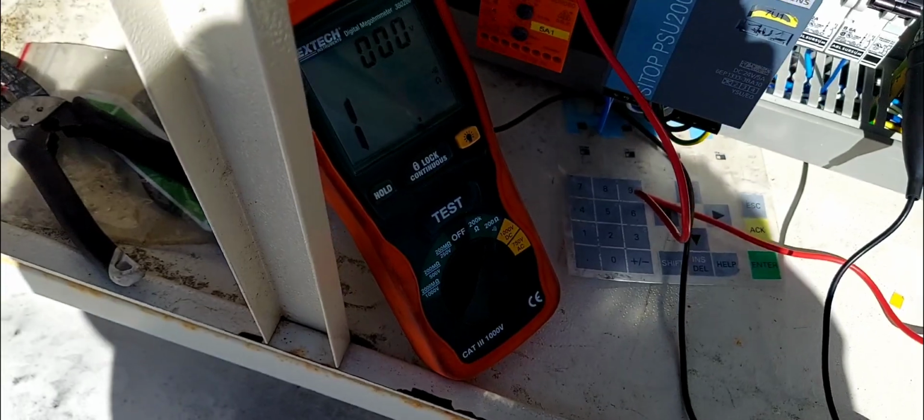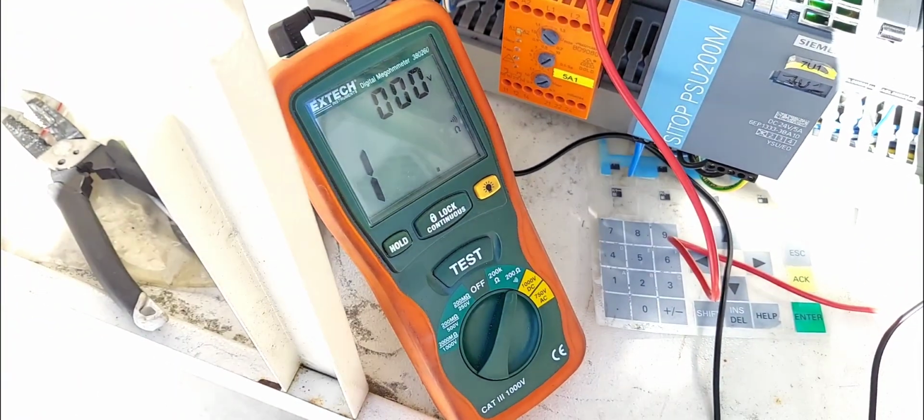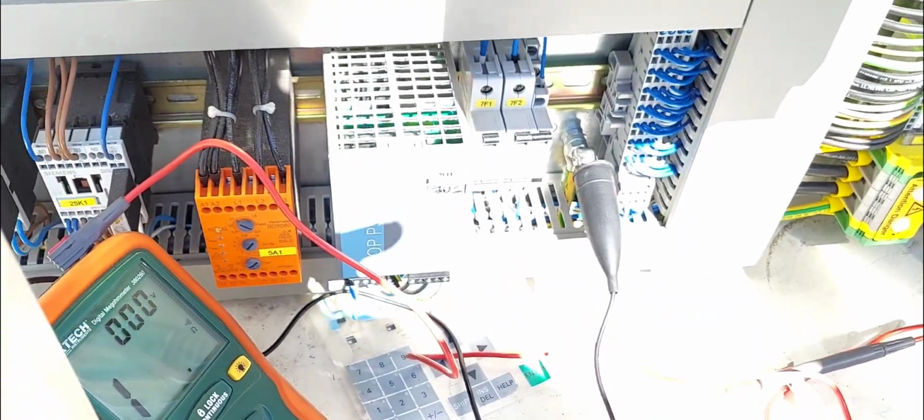Okay, so I have my meter all hooked up and ready to go. My negative probe, my positive probe. All right, so all ready for testing. I have the negative, the black, attached securely to the ground, chassis ground or any ground in the unit. You can go on your compressor discharge pipe or your suction pipe, any ground on the unit, because that's what you're testing.